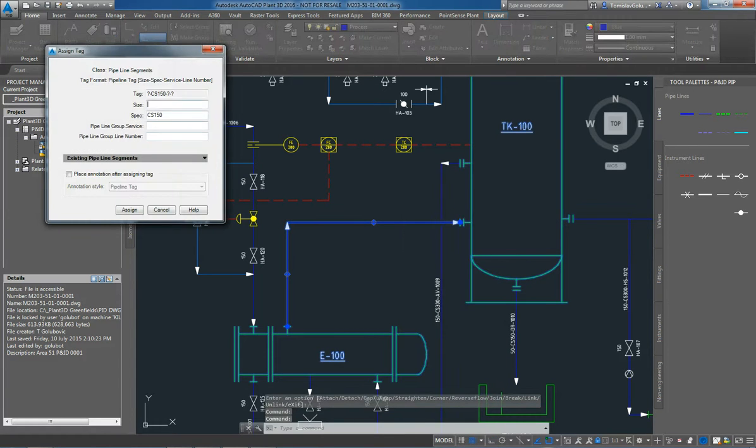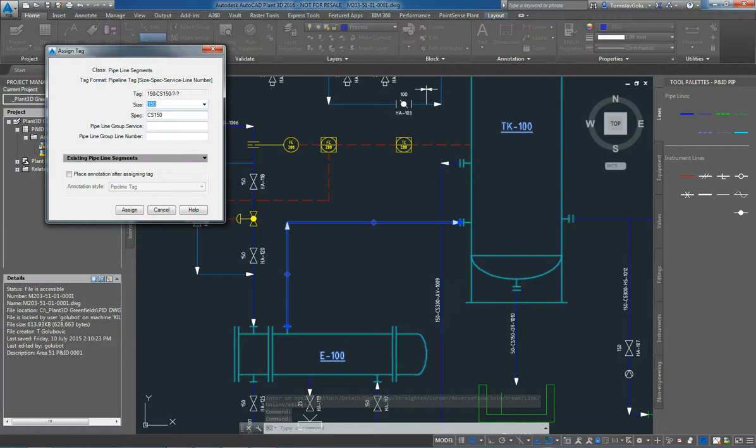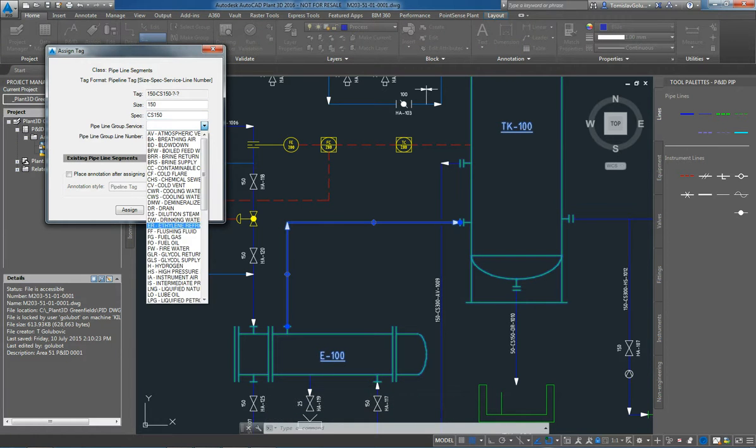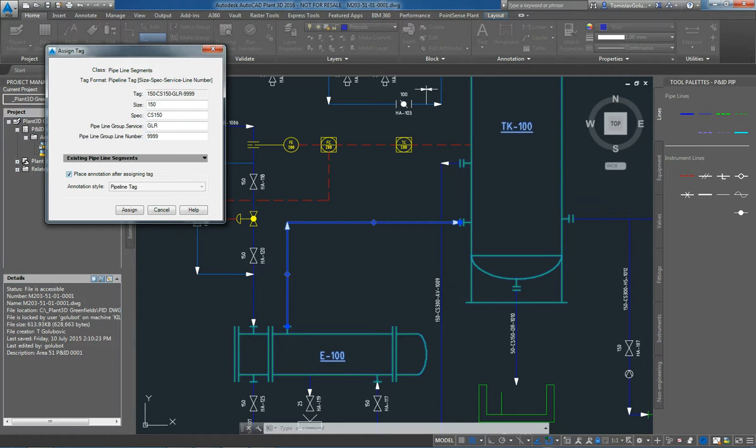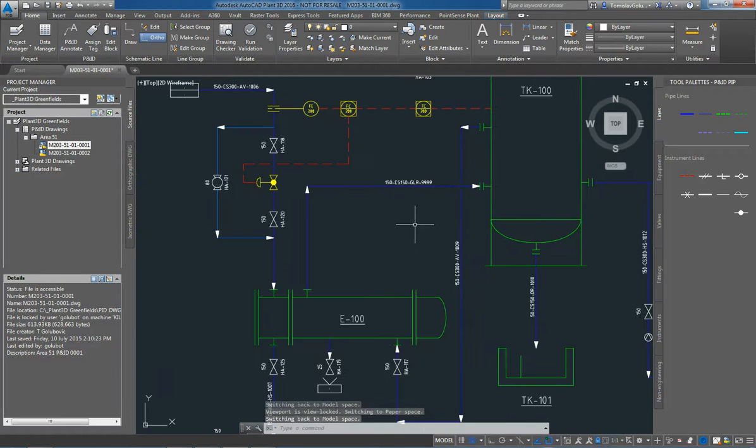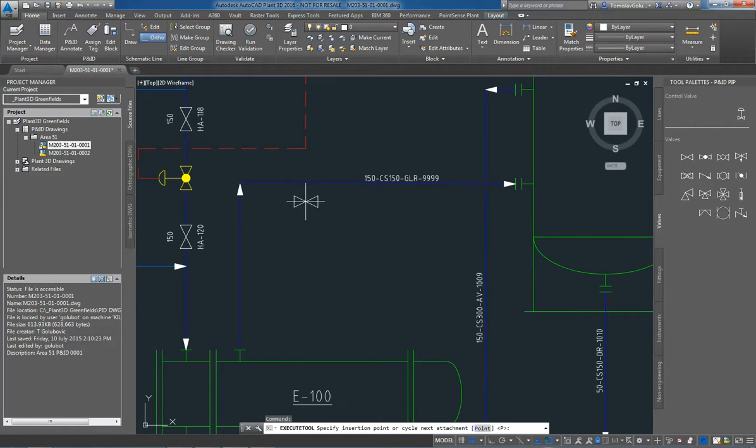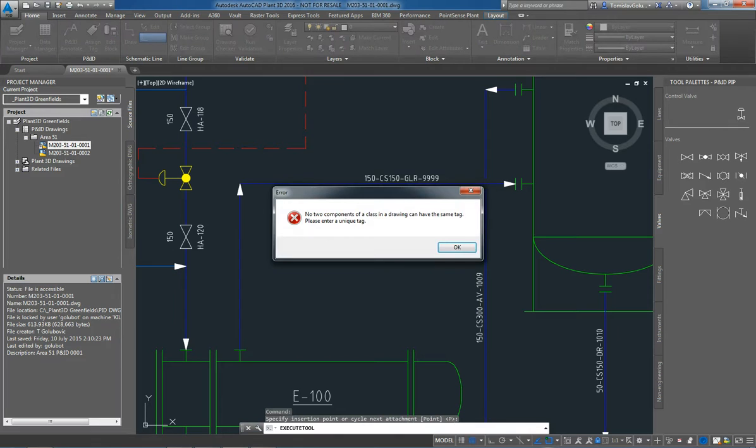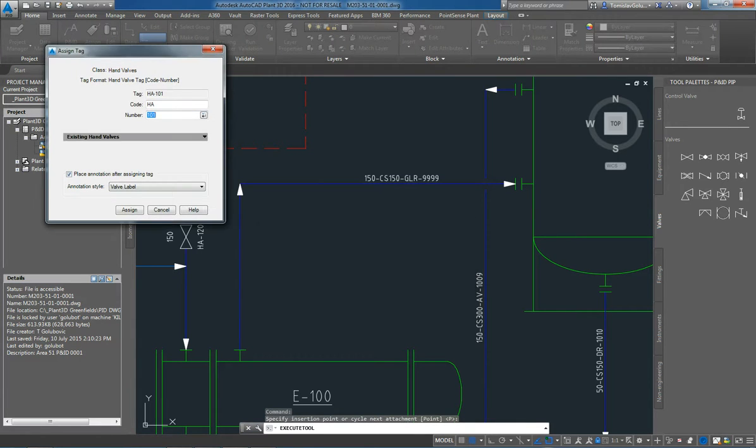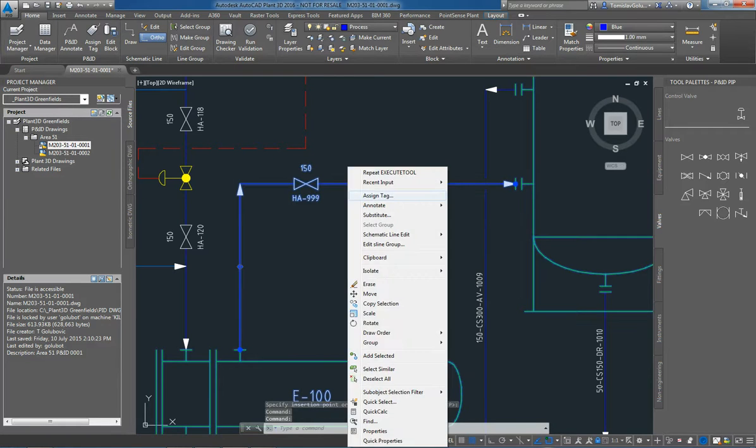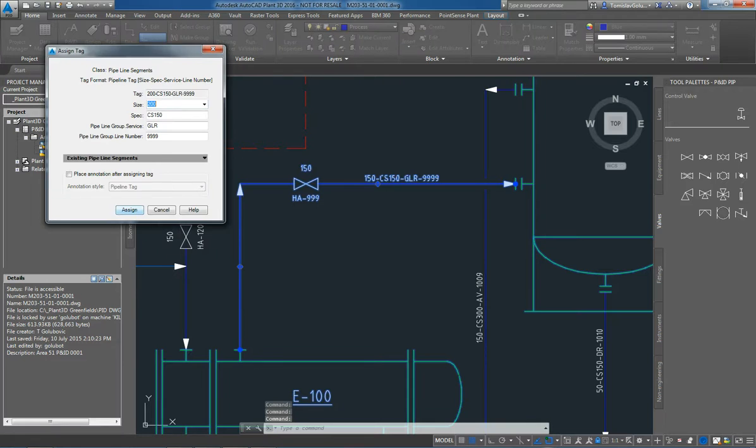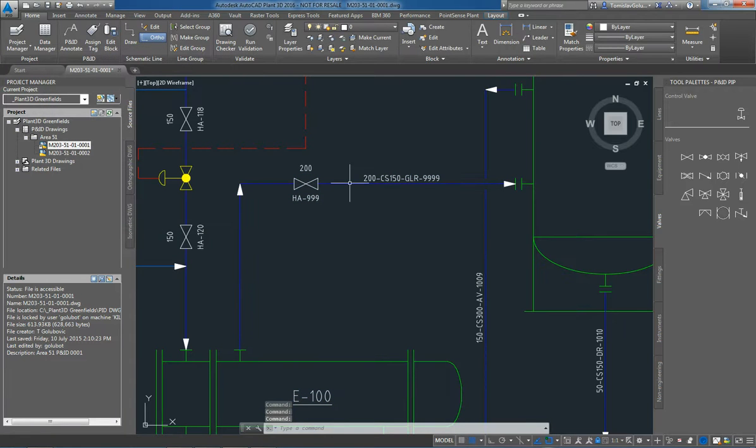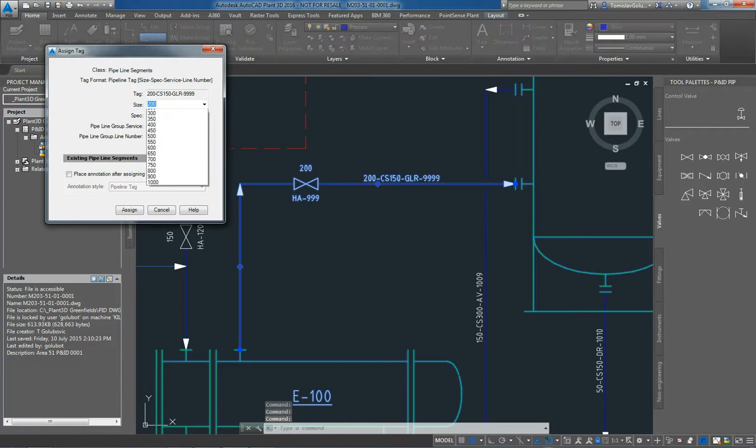Now I'm going to assign some metadata to it. I click on assign tag, I say that it's going to be a 6 inch line, the spec is carbon steel 150. I'm going to say maybe that it's a glycol return line, and I'm going to give it a line number 9999. At the same time, I can choose whether I want to place annotation or not, and I do in this case. So I do want to put the pipeline tag, and there it is there. Now that because I've placed the size, the spec, the service, and the line number, I can place valves on it. Now the software is telling me that I need to have a unique identifier for that valve, so I'm just going to give it the last line number that I think of. And there it is there. So now we have a 6 inch valve on a 6 inch line. If I change the pipeline size to an 8 inch, then the valve changes. So I'm just going to change that back to my 150.